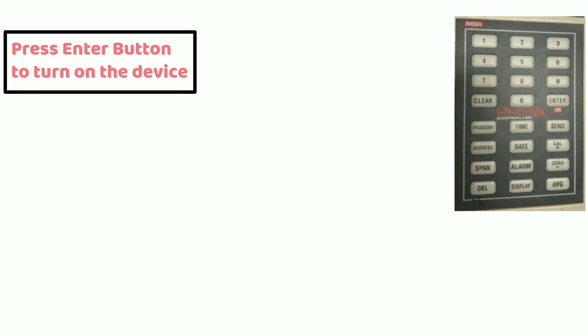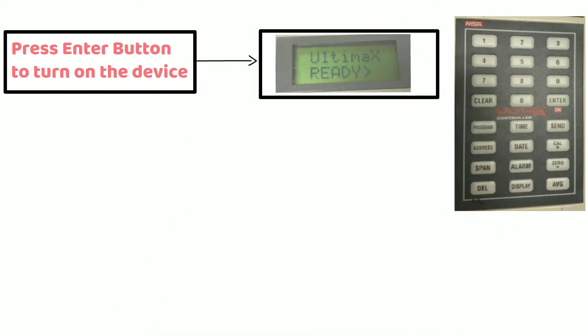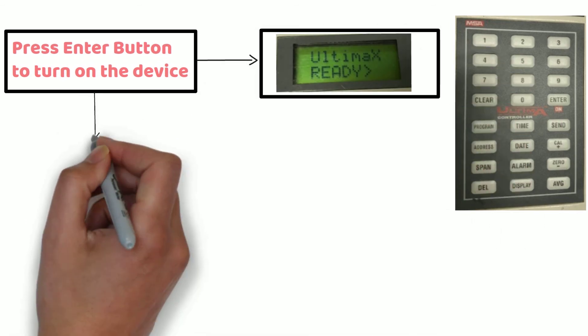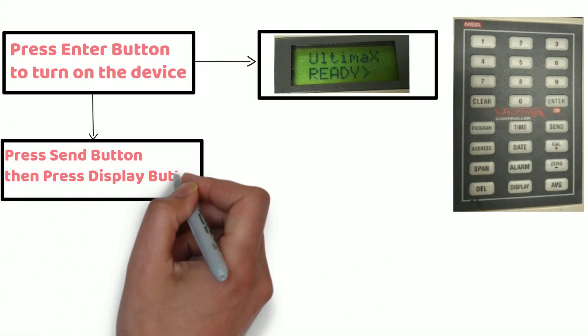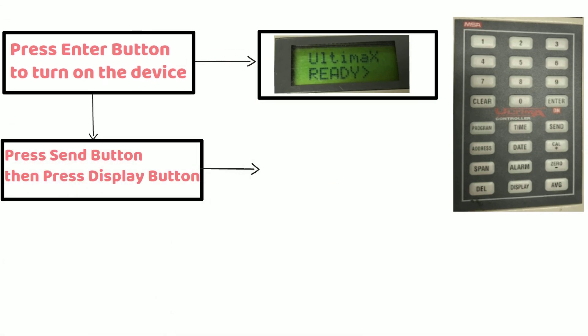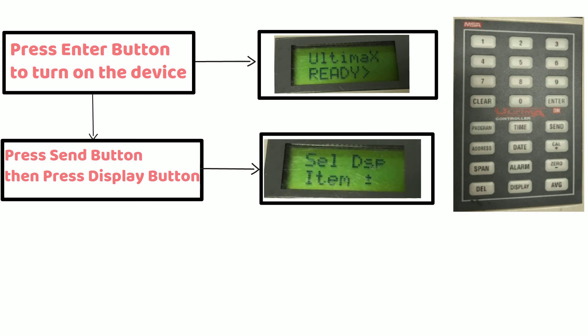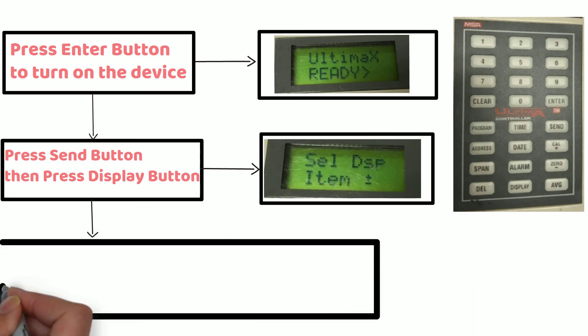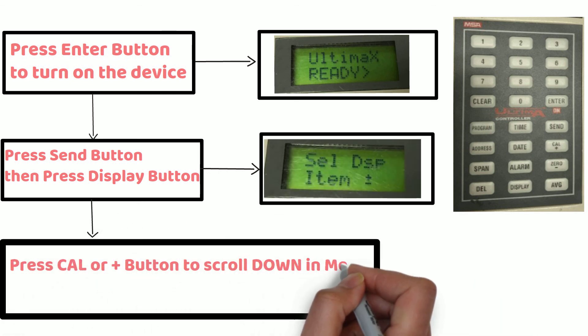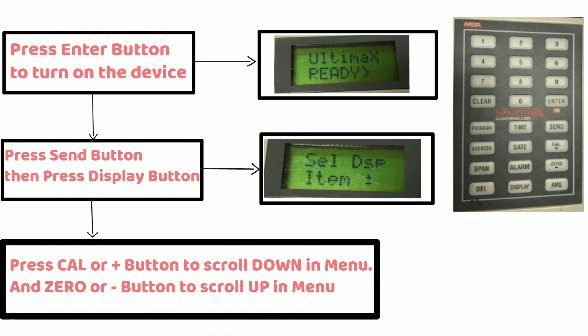First of all, press enter button to turn on the device. And you can see UltimaX ready on the controller display. Now press send button and then press display button. You can see select display item on controller display. At this time, press cal or plus button to scroll down through menu and press zero or minus button to scroll up in menu.